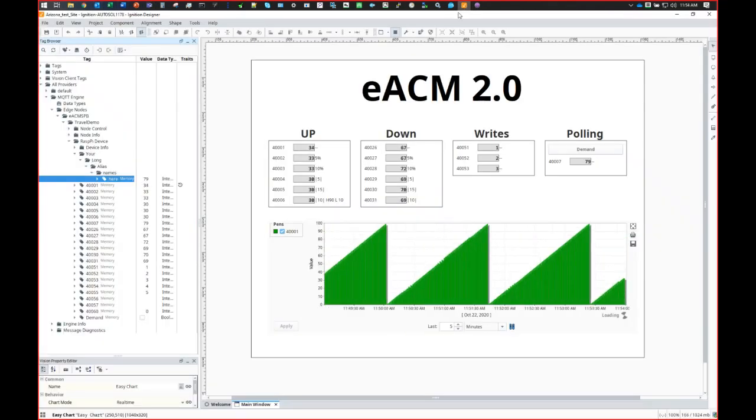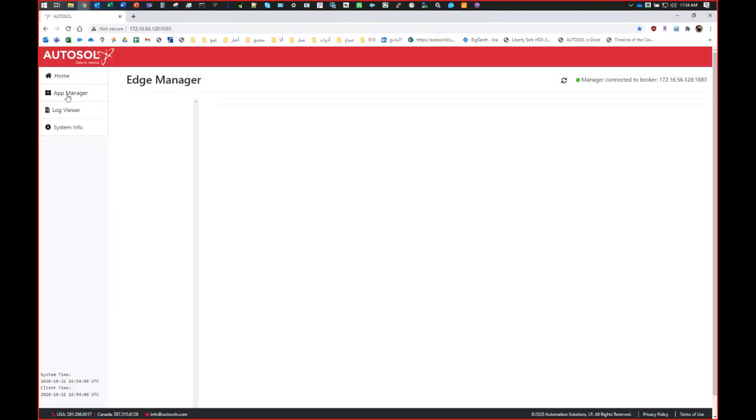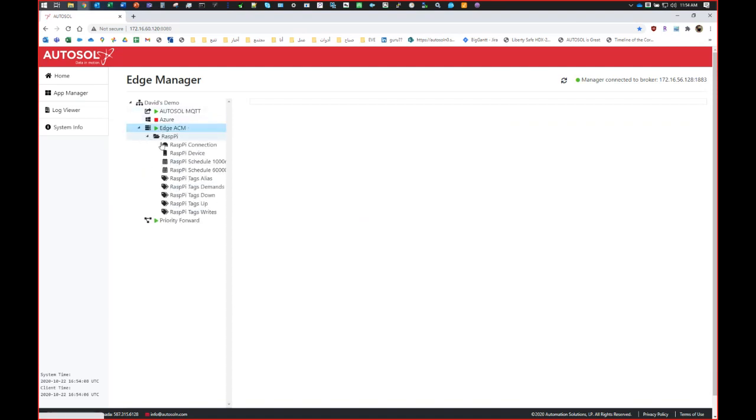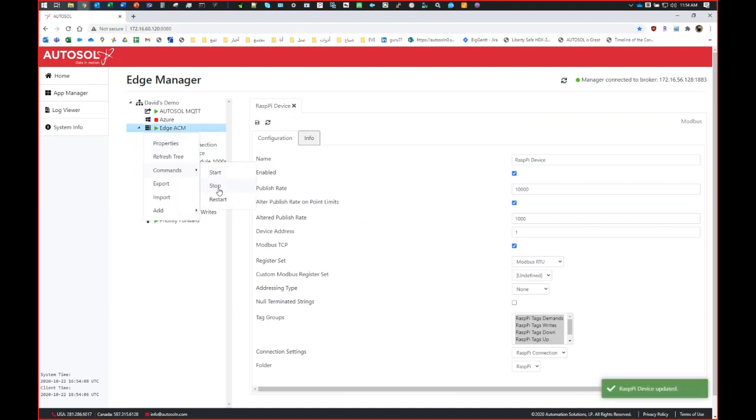Let me check this guy. Okay, so I am polling here. So if I go to the Edge device, let me just refresh him since, remember, I deleted everything and then I added everything back. You can change your poll and your publish rate. So if I'm going to poll in your example every half a second, I won't do it here because my Modbus simulator is made by me and it's not that good. It only updates every second.